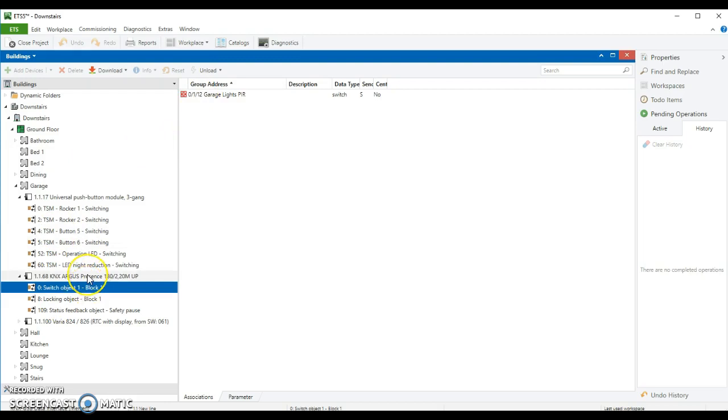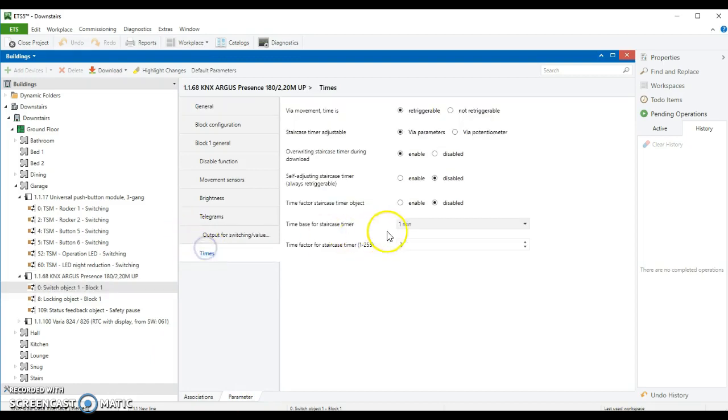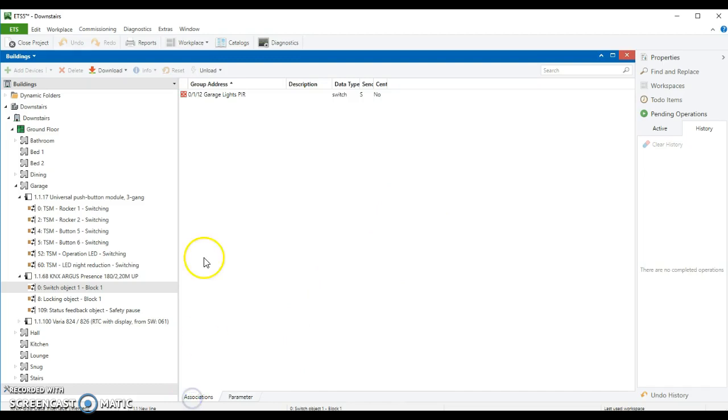And then when the timer runs out, and you can set the timer in here, if you look in the parameter somewhere. Yeah, so I've got the timer running out after two minutes. It will send a zero to this address and it will switch the lights off.